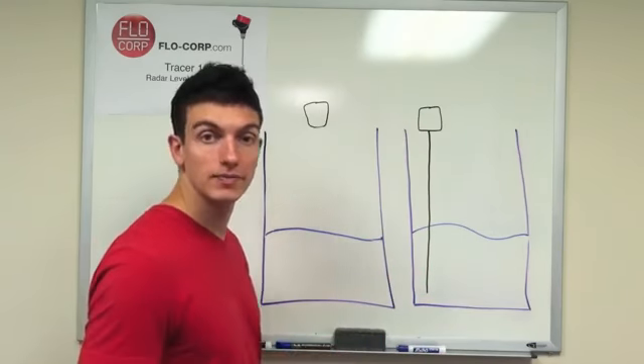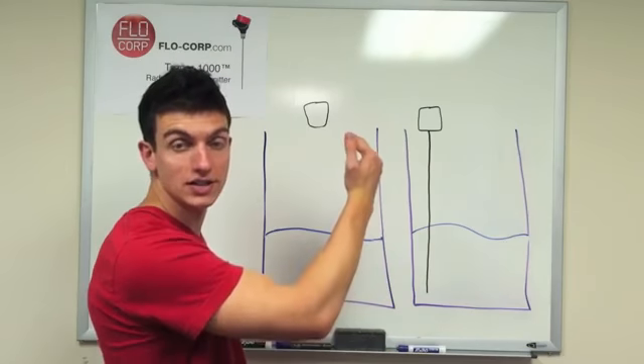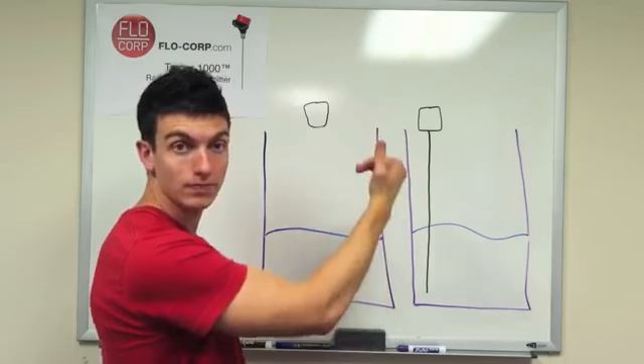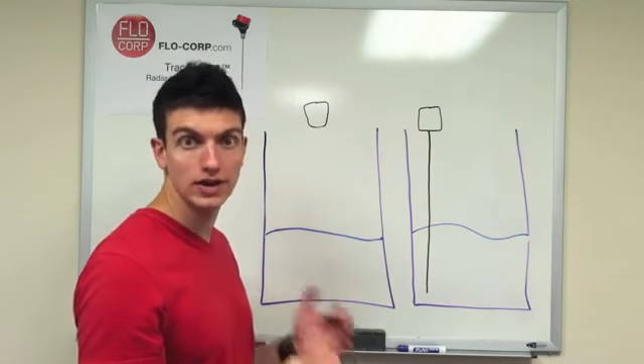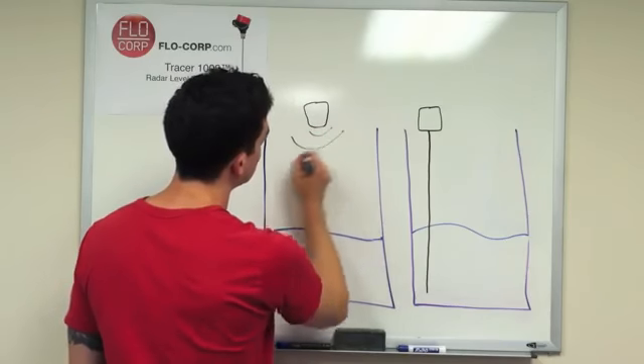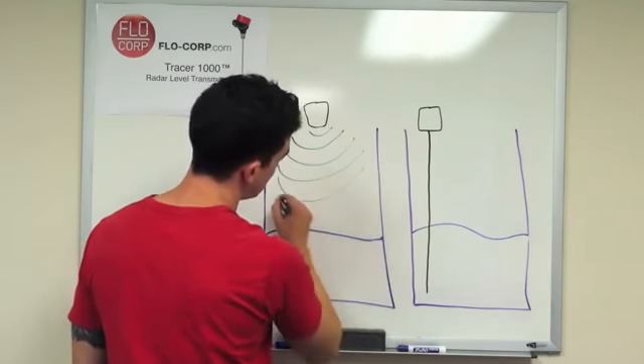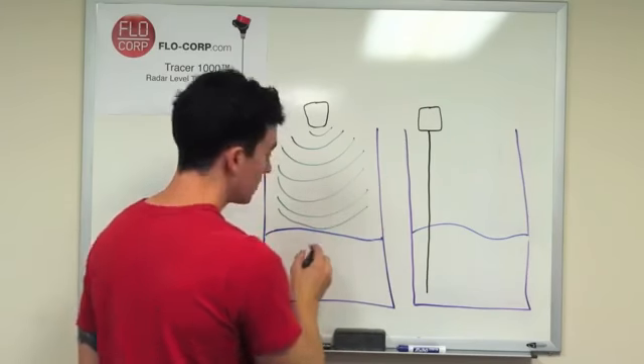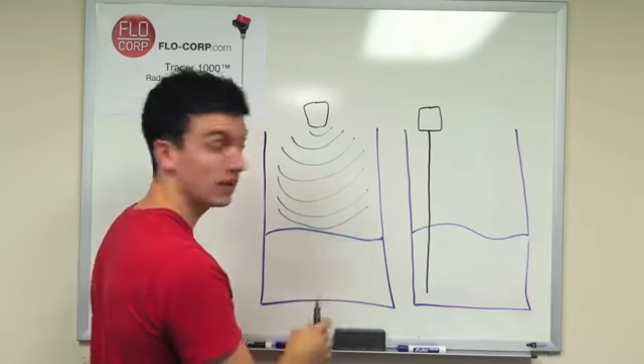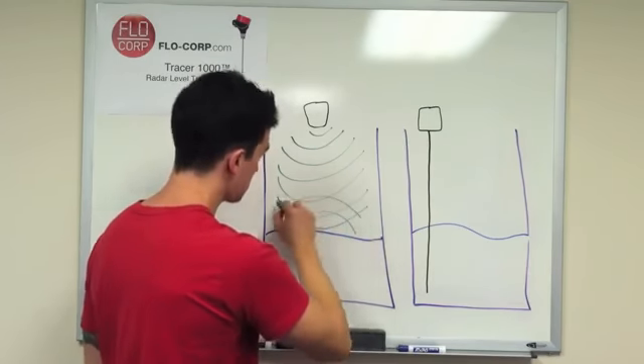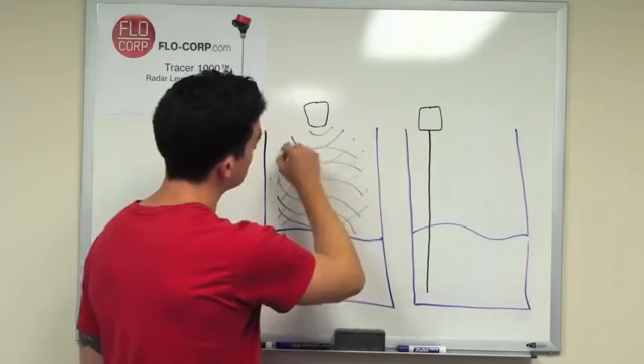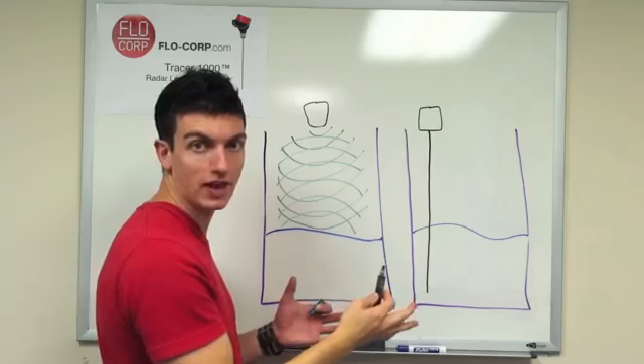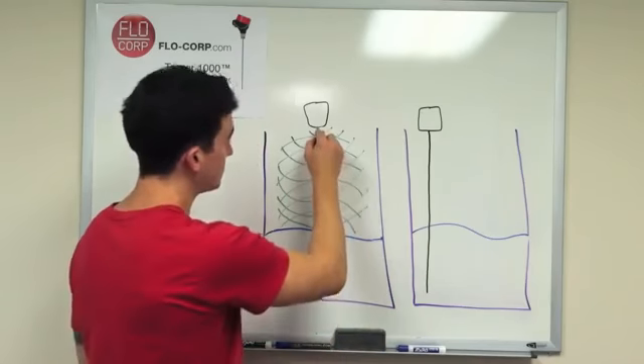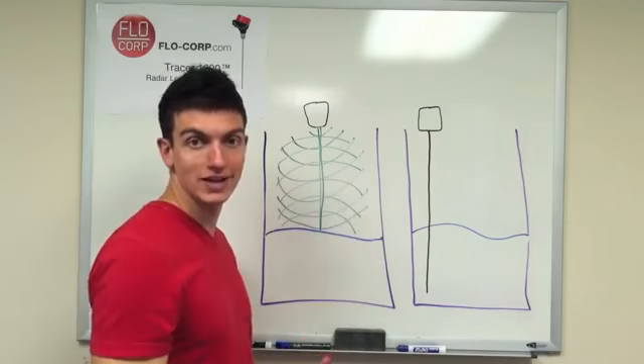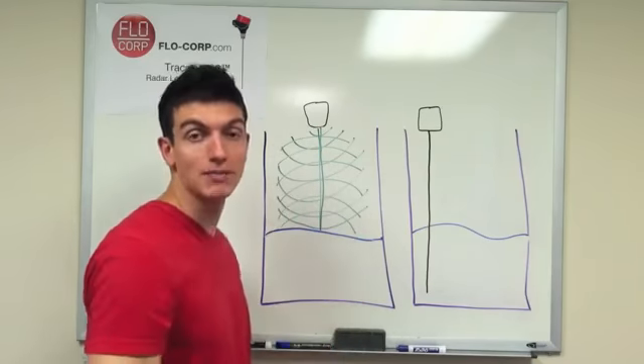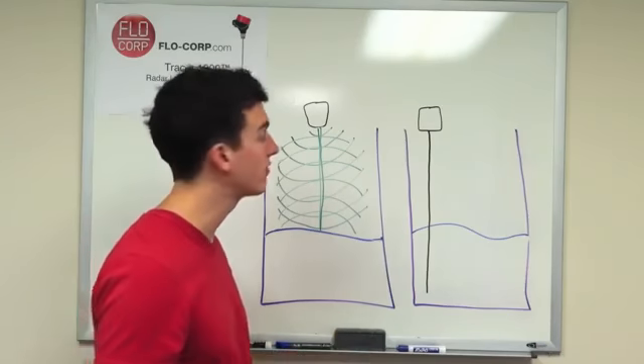Starting first with the ultrasonic, we're going to see how the sound energy is sent down to the liquid surface. It will echo and return back up to the transducer, and that's how we'll take our measurement. It'll strike the surface of the liquid and then return. And then we'll use time of flight here. Essentially the device would be programmed to understand this is how long it took two ways, and then it'll calculate the time for one way, and then it'll take a level measurement based off of that.